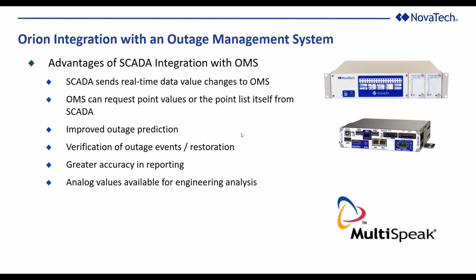You can have verification of outage events and restoration. If a device opened up, that's typically the starting point of the outage, and when that device gets closed in, that would indicate the moment restoration took place. You can have extra data in your OMS or in your outage records that tells you when a breaker opened or closed, which would serve as verification that it actually happened per your SCADA system. It's great for accuracy in outage reporting also, because for outages where the operating device or the protected device was a breaker or something SCADA is monitoring, suddenly we have exact timestamps of when that outage began and ended.